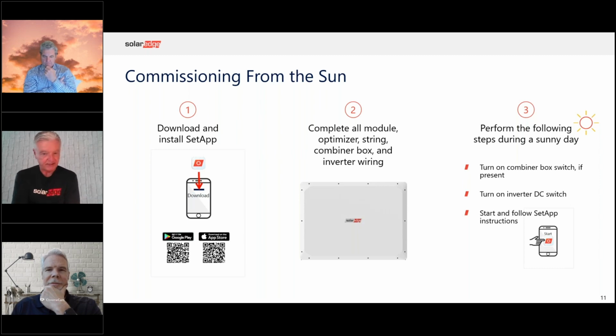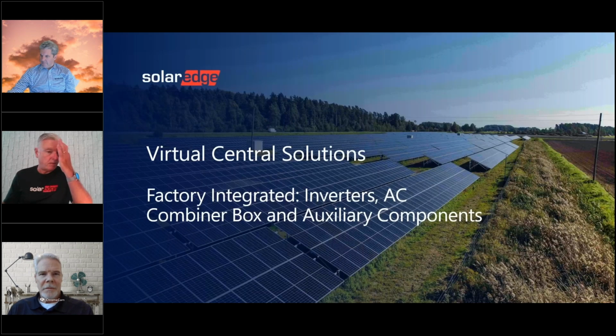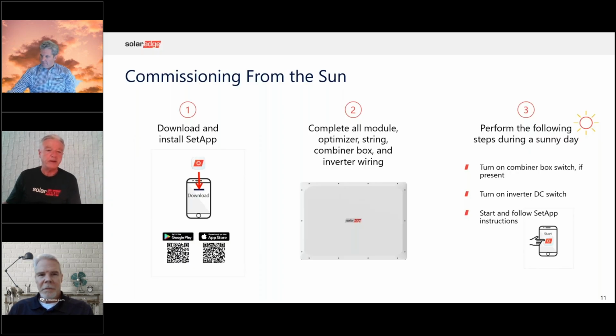So what that does is provides enough power to power up the communications card, and then you can go through the steps in SetApp to commission the inverter without having to have AC power present on the site. And many times on these ground mount sites, that's how it is. You don't have AC power present when you're already done with your installing of the inverters. So commissioning from the sun. On our other commercial inverters, we have pre-commissioning, and it's very popular. And this too is very popular.